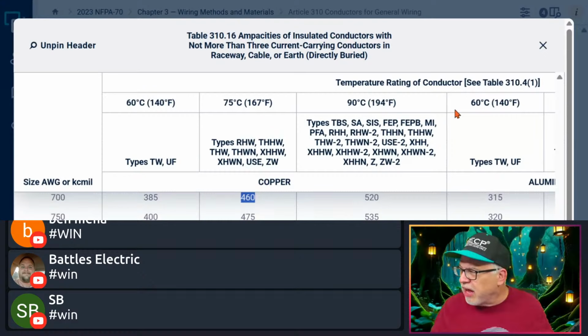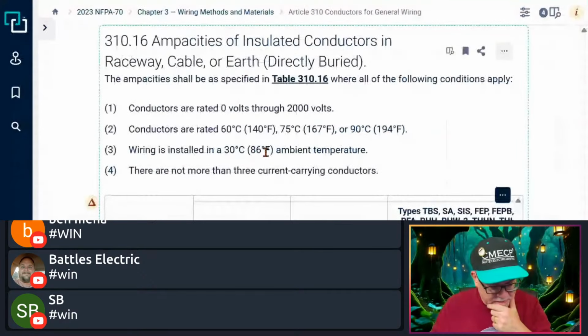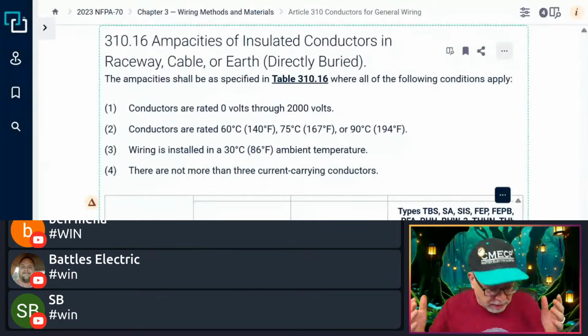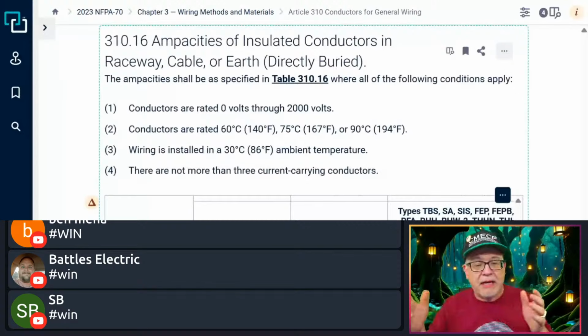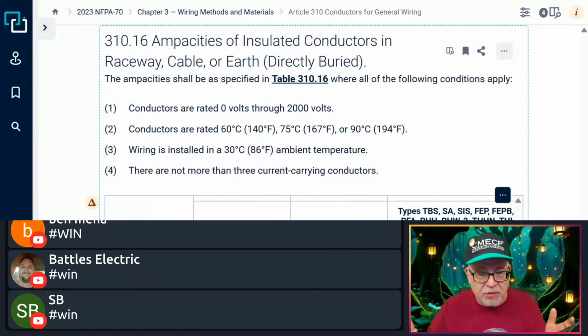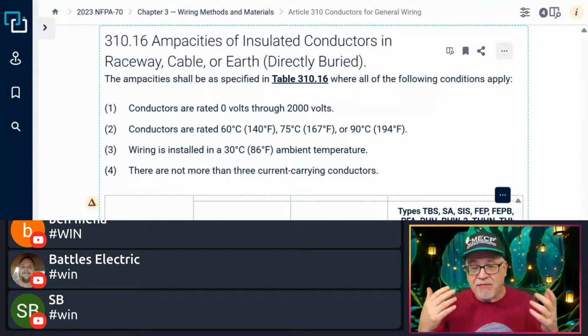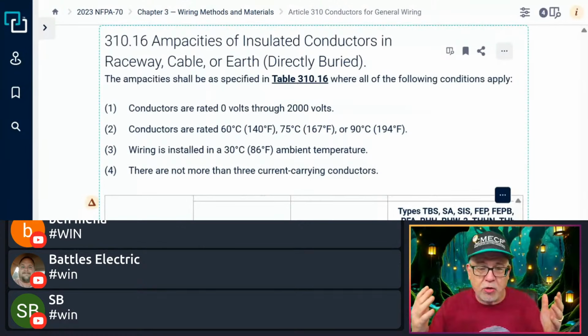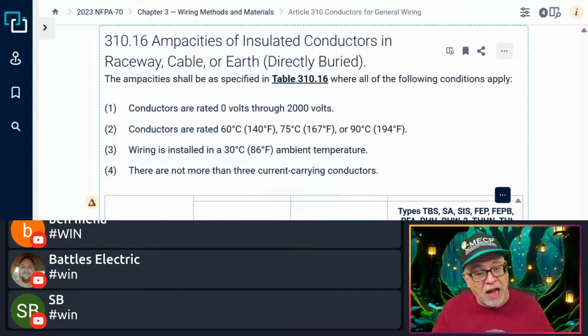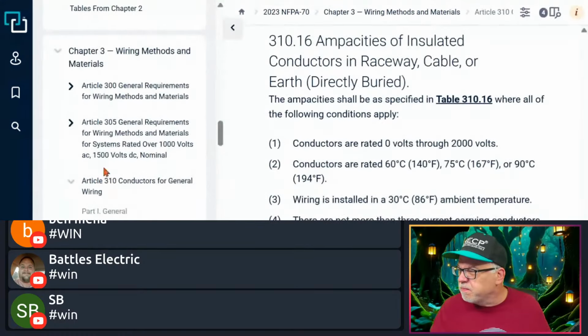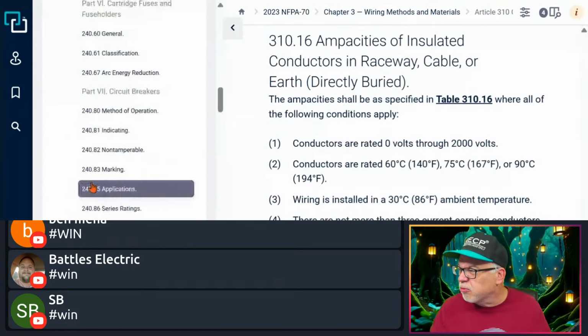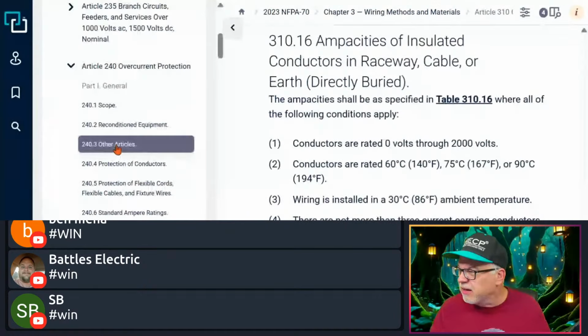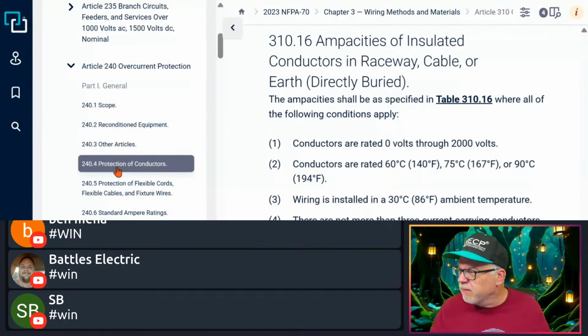Now, savvy guys like you say, okay, since it's 6 sets of 4-aught, I'm not going to have more than 3 current-carrying conductors in each raceway. Nobody told me anything otherwise, so there's not going to be any adjustment or correction. It didn't say anything about ambient temperatures, anything like that. Doesn't mean that you may not have ambient temperatures, but in this question, all it wanted to know about was ampacity. So the only plausible answer is going to be 6 sets of 4-aught. That's going to give me at least the 1200 that I need. All right, so just to round this out, you want to go look at the rule that I told you, right? And again, here it is, 240.4.